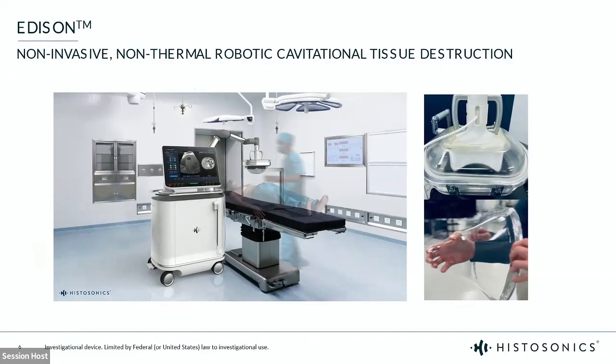What you see on the right of the screen is this membrane that holds the liquid that's going to be between the treatment head and the patient. And this is a special fabric material that does not absorb ultrasound. So it's like you're doing the treatment without any absorption. Inside this membrane, there is degassed water that allows us to target the lesion precisely and then treat it.